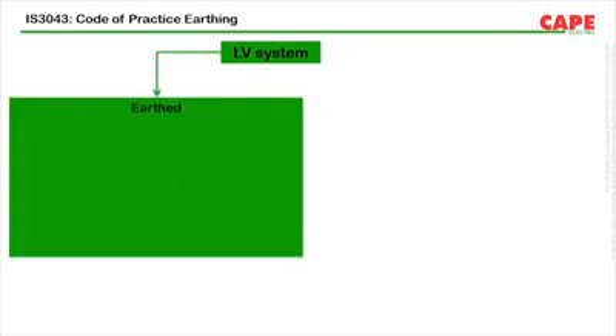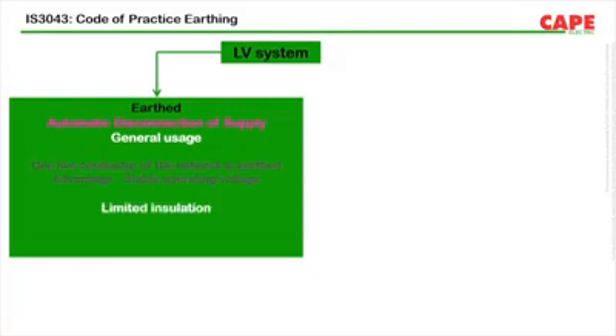Two types of basic systems can be followed in an installation, and the rules to be followed are explained in IS 732 and IS 3043. Earthed system and unearthed system. In an earthed system, safety is achieved by automatic disconnection of supply. The ADS shall work within the time specified in these standards.